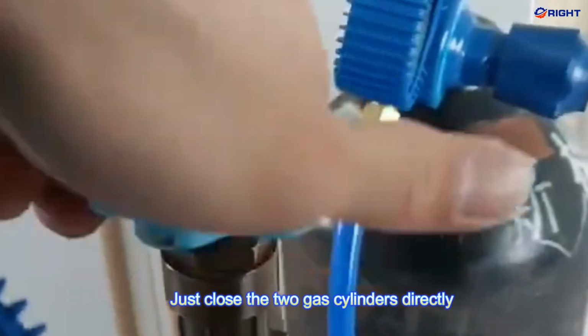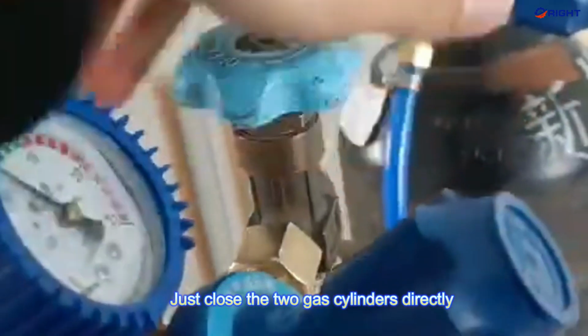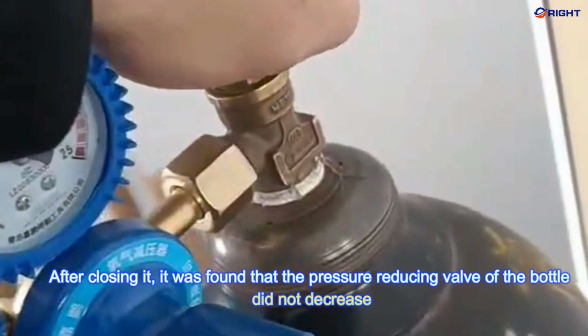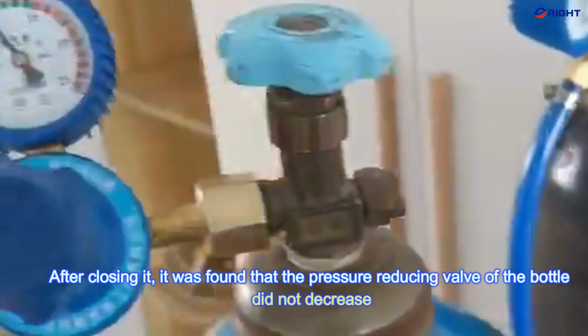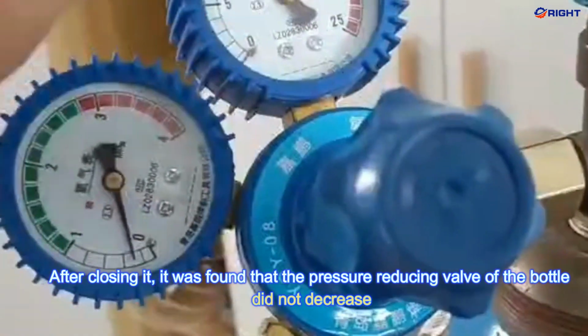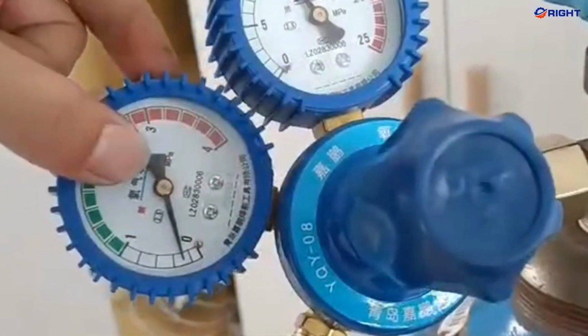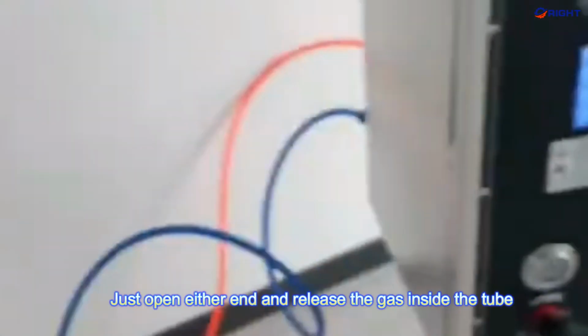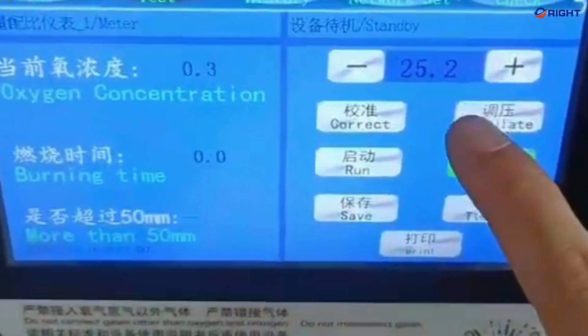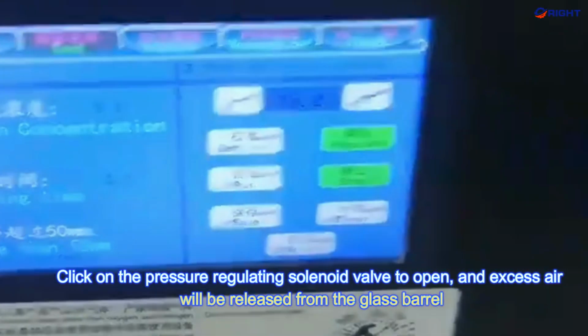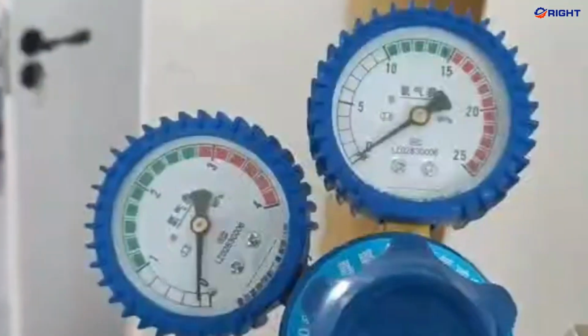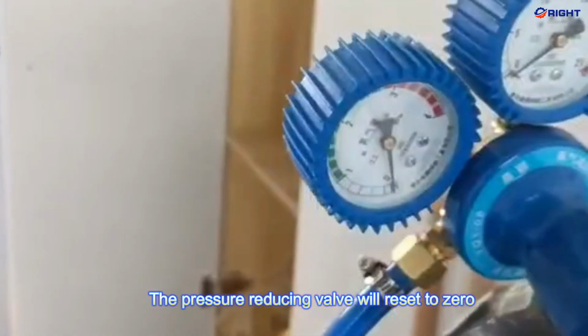Just close the two gas cylinders directly. After closing them, you will find that the pressure of the pressure-reducing valve does not decrease. Just open either end and release the gas inside the tube. Click on the pressure-regulating solenoid valve to open, and excess gas will be released from the glass barrel. The pressure-reducing valve will reset to 0. Close the pressure regulator again. Shut down.